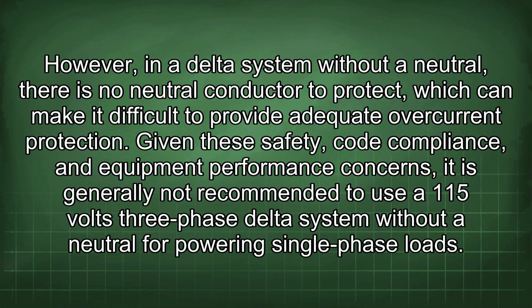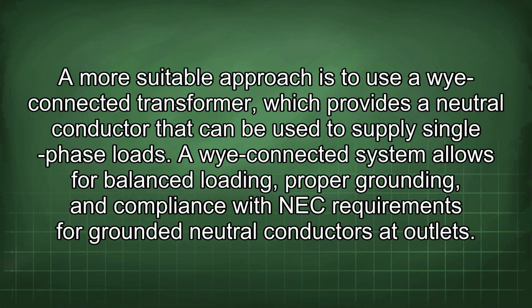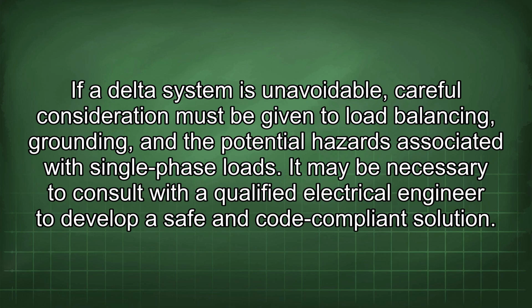Given these safety, code compliance, and equipment performance concerns, it is generally not recommended to use a 115 volts three-phase delta system without a neutral for powering single-phase loads. A more suitable approach is to use a Y-connected transformer, which provides a neutral conductor that can be used to supply single-phase loads. A Y-connected system allows for balanced loading, proper grounding, and compliance with NEC requirements for grounded neutral conductors at outlets. If a delta system is unavoidable, careful consideration must be given to load balancing, grounding, and the potential hazards associated with single-phase loads. It may be necessary to consult with a qualified electrical engineer to develop a safe and code-compliant solution.